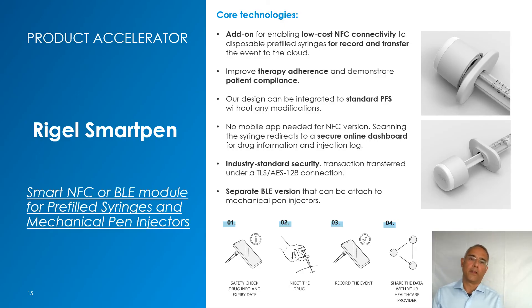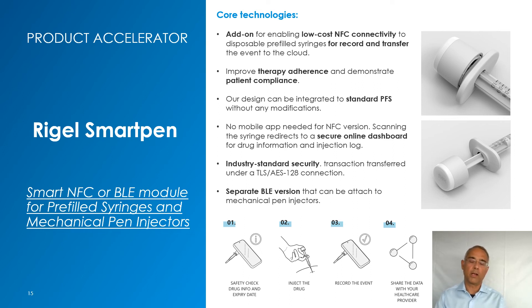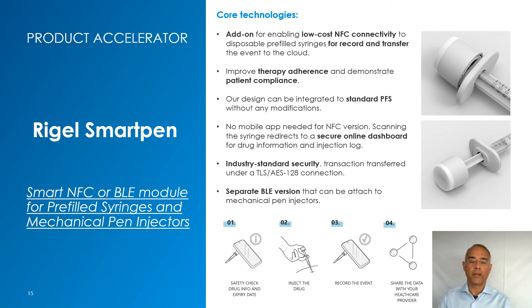Rigel is the internal code name for this smart pen project. It is an electromechanical add-on that can be snapped onto a pure mechanical syringe to create connectivity — either a very low-cost solution based on NFC technology, or something more complex with Bluetooth connectivity and connection to an app and cloud system. Let's have a look at how it works.